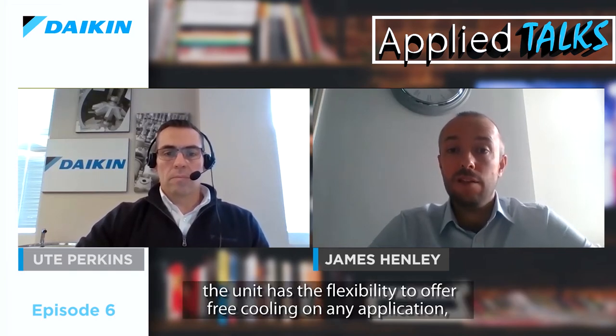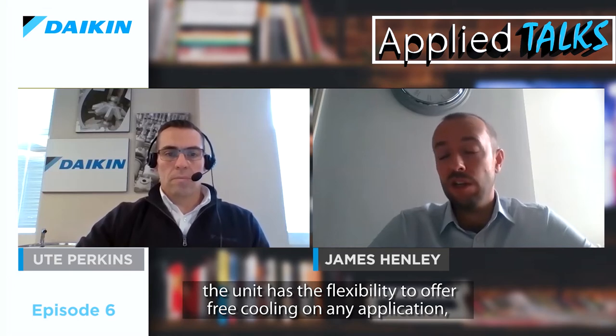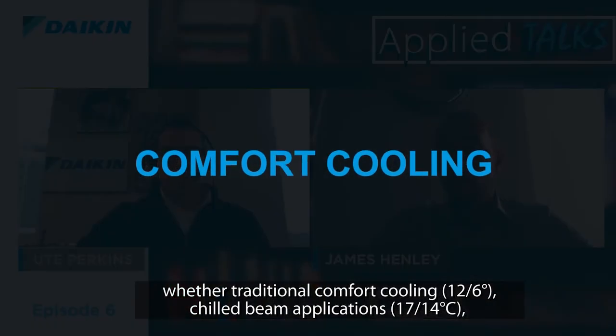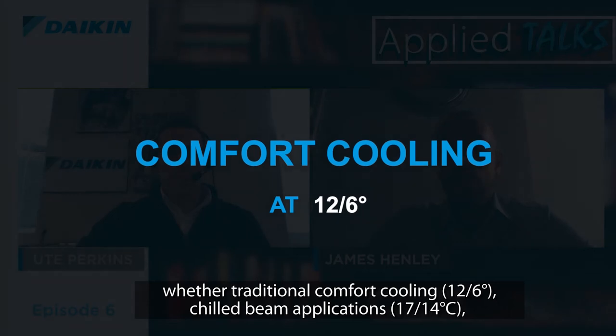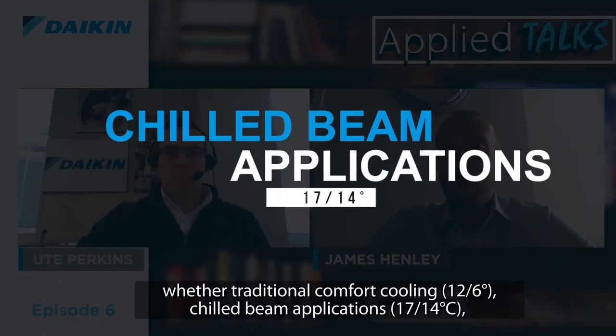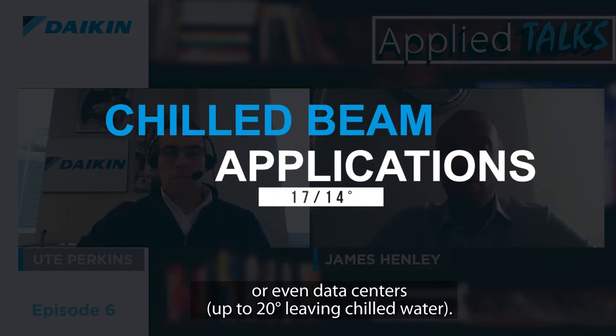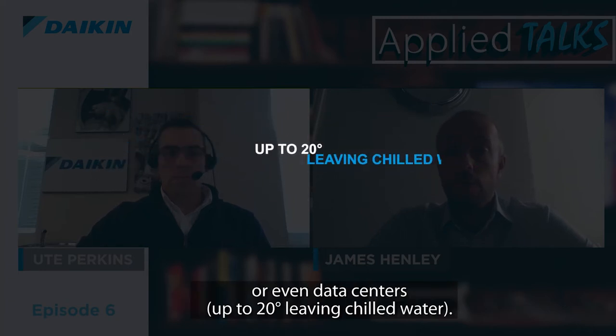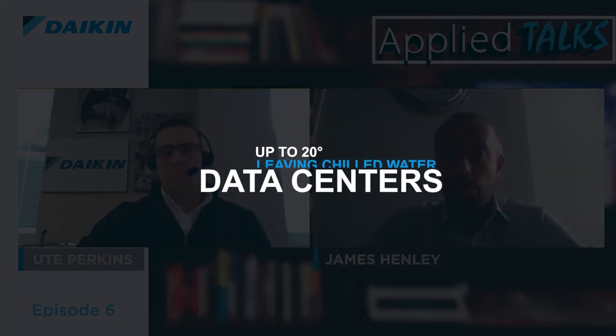The unit has the flexibility to offer free cooling on any application, whether that's traditional comfort cooling at 12/6, chilled beam applications at 17/14, or even on data centers up to 20 degrees chilled water leaving temperature.